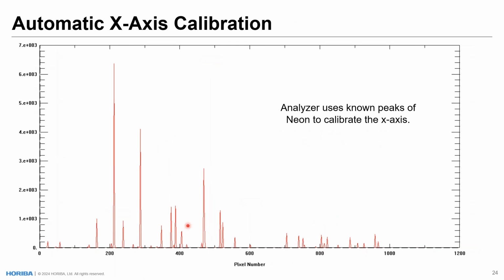Likewise, an automatic x-axis calibration happens routinely throughout collection in an online setting. So this is an emission spectrum of neon, and the analyzer uses known peaks of neon to calibrate the x-axis. All of our analyzers, laboratory or online, come with a neon card in its spectrograph, and this neon card is triggered on and off as another internal reference in our analyzer to calibrate the x-axis energy positions, which correlates to the pixel locations on our camera. So that's always accounted for as well.